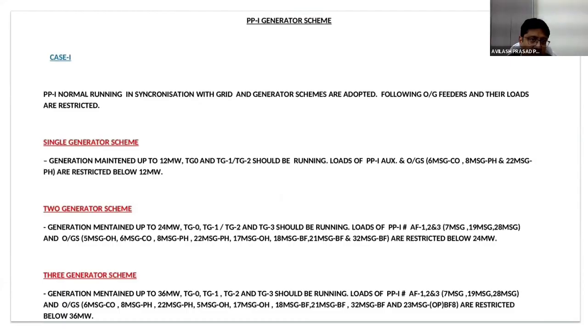do a case study. Suppose there is a case one where PP-1 is running normally in synchronization with the grid, and generation schemes are adopted, and the following outgoing feeders and their loads are restricted. Suppose, as we said, we have 4 generators and a single generator is running. Then generation is maintained up to 12 megawatt, TG0 and TG-1/TG-2 should be running. Loads of PP1, auxiliary and outgoing 6MSG-CO, 8 MSG PH, 22 MSG PH are restricted below 12 megawatt. These are some locations or loads which are restricted below 12 megawatt. Two generator schemes, where generation is maintained up to 24 megawatt, TG0, 1, 2, 3 should be running.